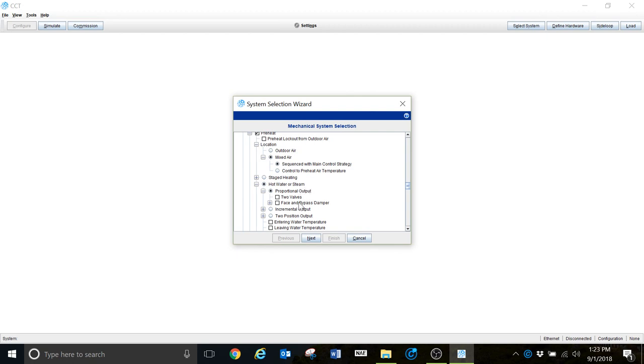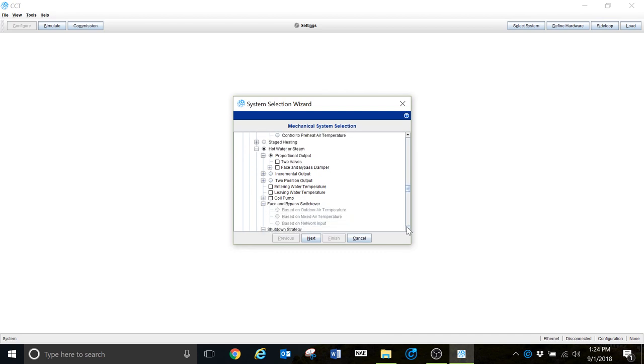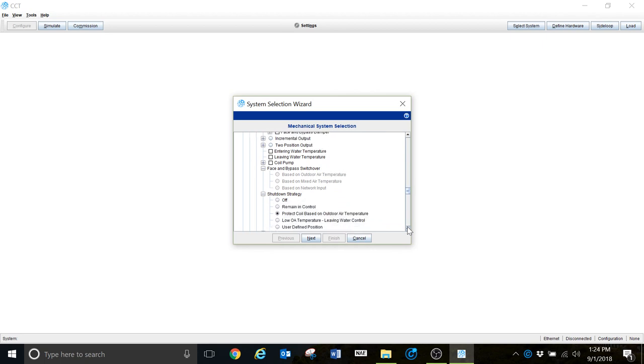We do have hot water or steam proportional output for the type of actuator we're going to use. There are options for a two valves, face and bypass damper. Some air handlers will have valves as well as a face and bypass damper. Some air handlers have everything in line — the hot water coil prior to the chilled water coil — and when heat isn't needed the hot water valve is simply shut. We'll leave a lot of standard options as we scroll down.